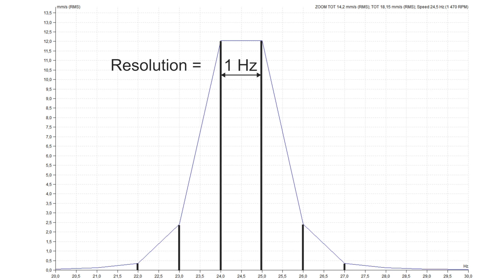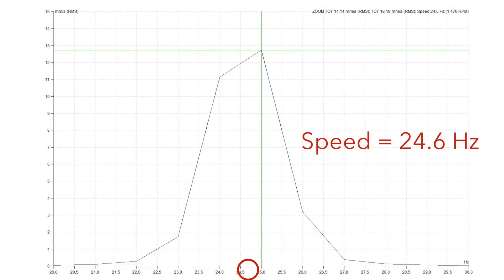But the frequency of machine vibrations may have an unlimited number of values. For example, the machine speed frequency is 24.6 Hz. But the spectrum contains lines on 24 Hz and 25 only. We get this shape of spectrum — the peak is on 25 Hz, which is the nearest line.